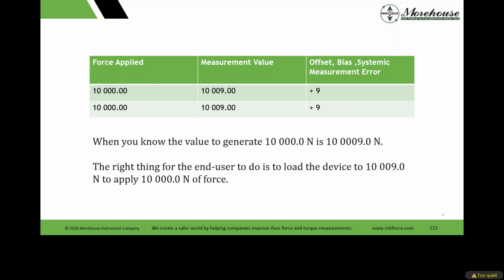So what we end up knowing is that if we apply 10,000 and our indicator reads 10,009, we say, okay, let me do it again. We apply 10,000, indicator reads 10,009. Guess what? We apply it again and it reads 10,009. I have a bias. So the right thing to do with this bias is correct for it. And correcting for it means that the technician, to generate 10,000, loads the device till it reads 10,009, thus defeating the whole purpose of TEDS in these span points, because the only point I got was when I did 0 and 100% was at 25,000 when I did the 2-point span.